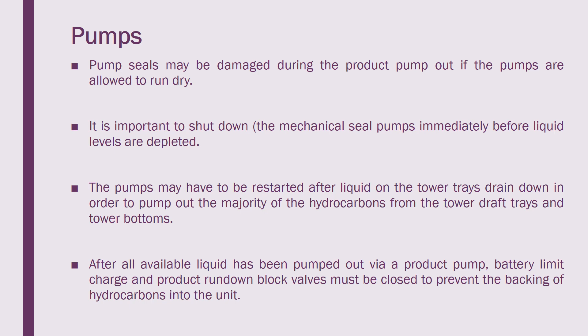The pumps may have to be restarted for liquid or tower tray drain-down in order to pump out the majority of hydrocarbon from the tower draw tray and the tower bottom. For example, in a distillation column, we cannot allow the mechanical seal pump to run until the bottom of the column is completely empty - we keep some amount of liquid on the safe side to safeguard the suction. At the same time, we must ensure all the tray liquid reaches the bottom of the column. If it is not reaching, we have accumulation inside the column and it is not 100% cleared. We must allow the tray liquid to reach the column bottom, then restart the pump.